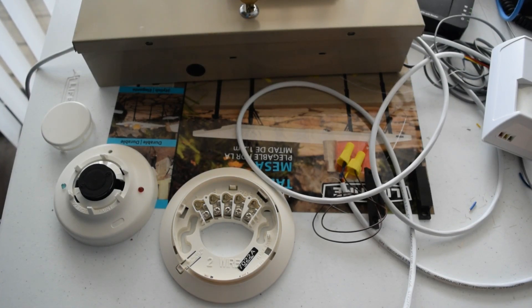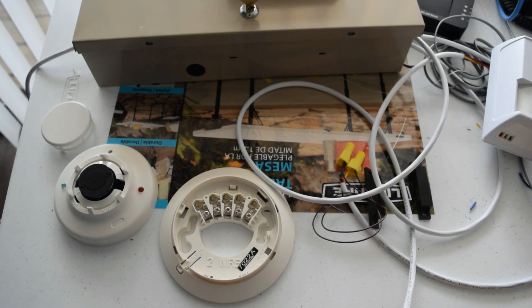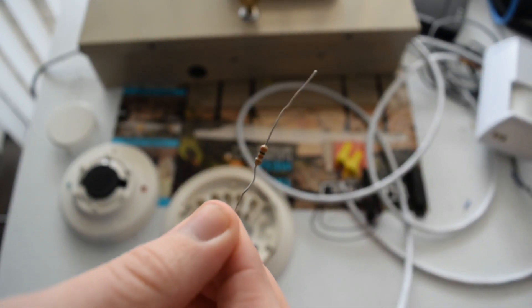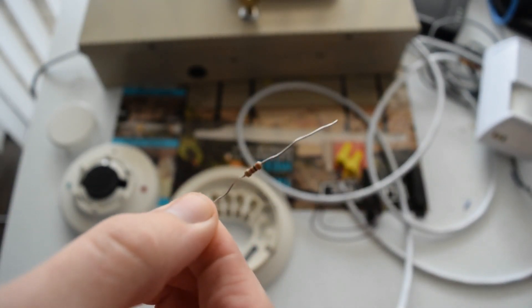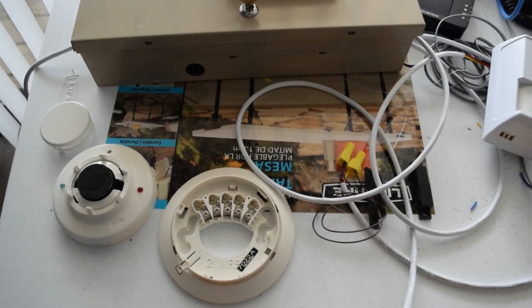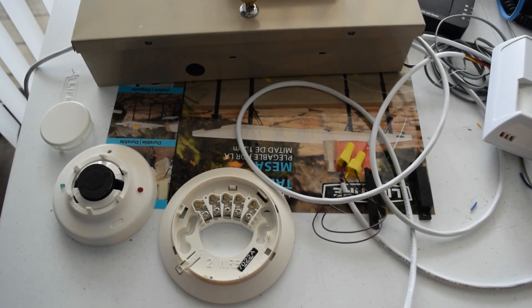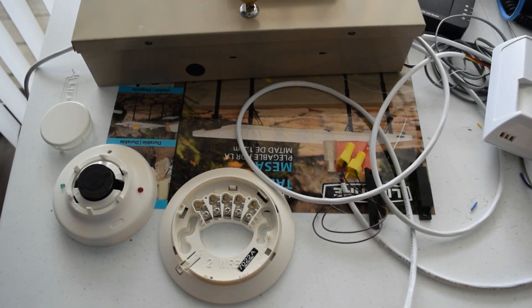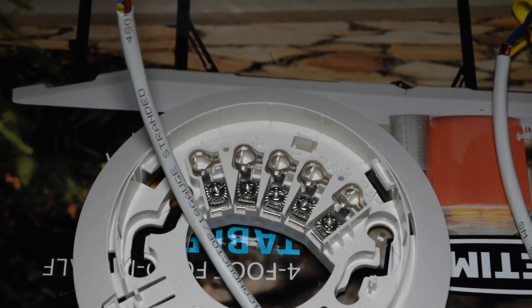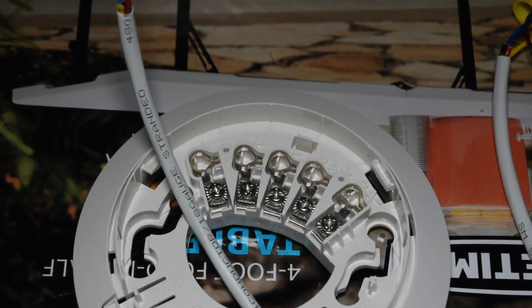Because if you don't, the panel is just going to keep throwing off troubles at you. It doesn't know that the smoke detector is there. And basically the resistor is the only way it can tell that the smoke detector is there. So just like I mentioned that the zone is not going to function correctly on the system without a resistor being there. For the first time in this series of videos, we are going to be using a resistor.